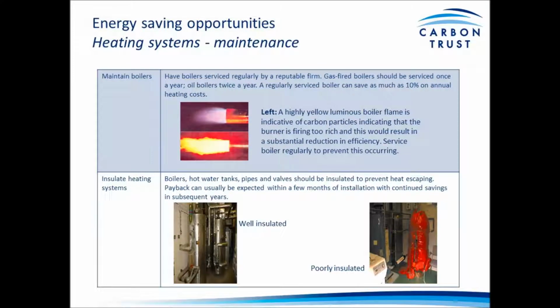For heating systems, moving on to maintenance, which is key to their efficiency. You should really be looking to service your gas boiler once a year and oil boilers twice a year. And make sure the maintenance provider is checking and reporting the efficiency to you. Good maintenance can easily save in excess of 10% of your fuel consumption. The example diagram here shows clean burn at the top versus dirty burn at the bottom. So the highly luminous flame is indicative of carbon particles. So it's burning too rich and results in a substantial reduction in energy efficiency. And servicing boilers should help avoid these, again, relatively hidden inefficiencies.